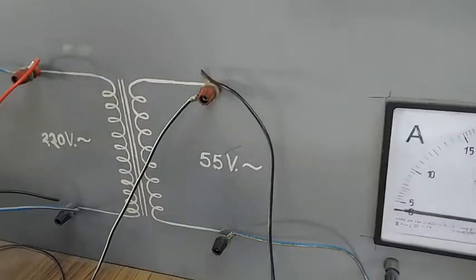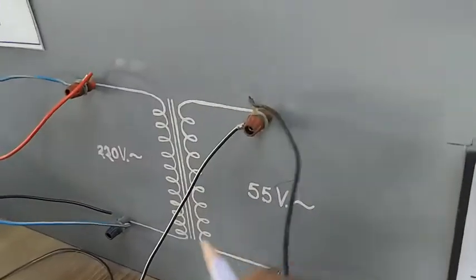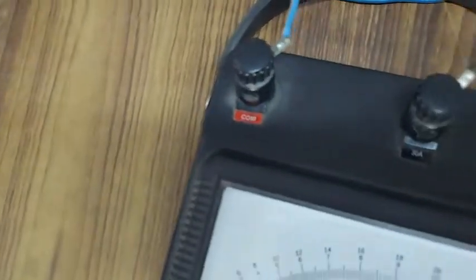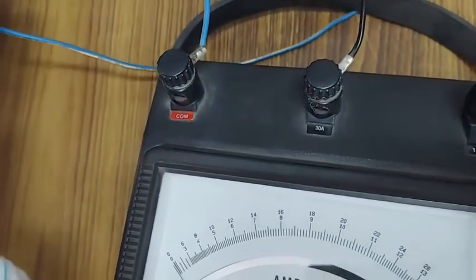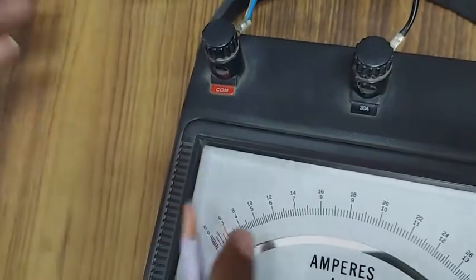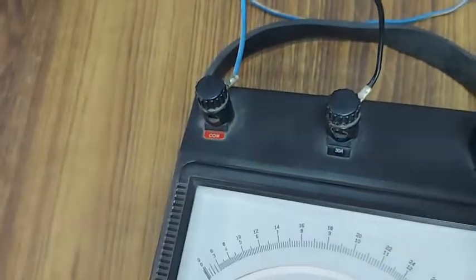And in the secondary side, that is in the low voltage side, that is 50 volt side, 55 volt side, we will connect one ammeter as we have told. So one point from the positive terminal of the 55 volt is coming to the 30 ampere range, and the negative point of that point of the secondary coil is coming to the common point. So we can see here in the common point it's connected.